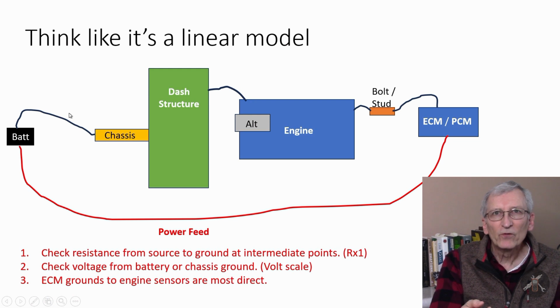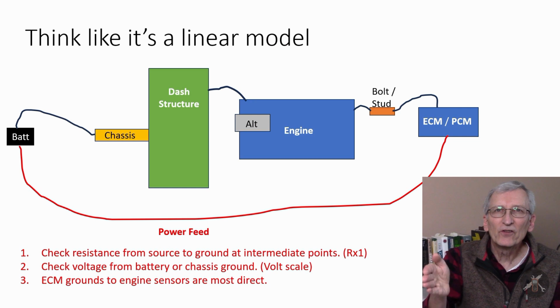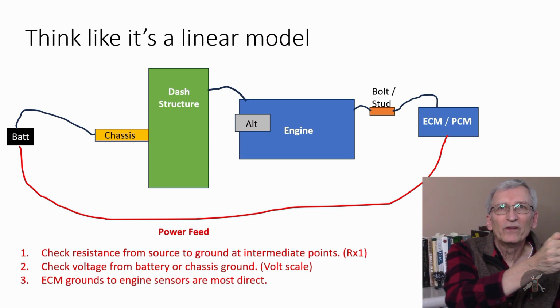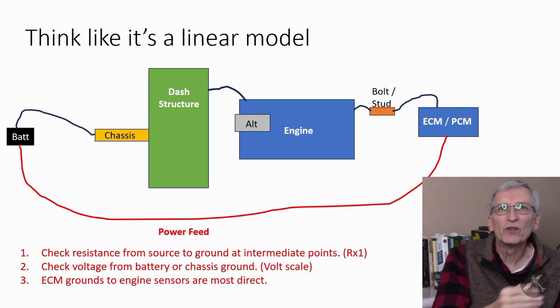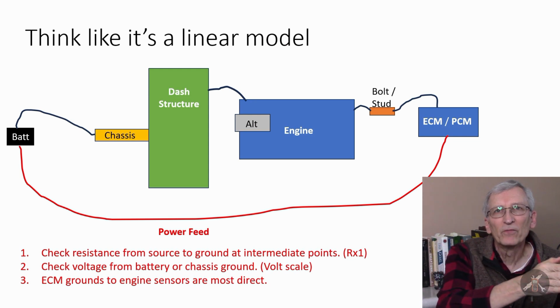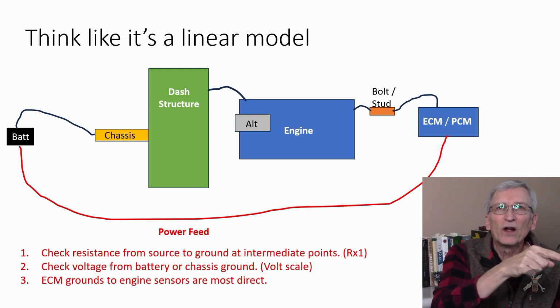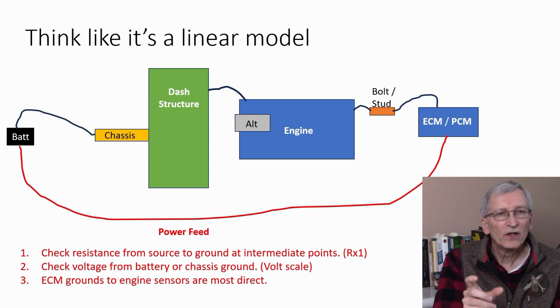The second side would be, with your system powered up in voltmeter mode, do you see voltage on that terminal? And if you do, how much is it? Then as you go downstream, can you tell where the voltage drop is? Because current is flowing through the circuit, and you'll get a voltage drop through any resistance you see, and you're looking for where the bad spot is.